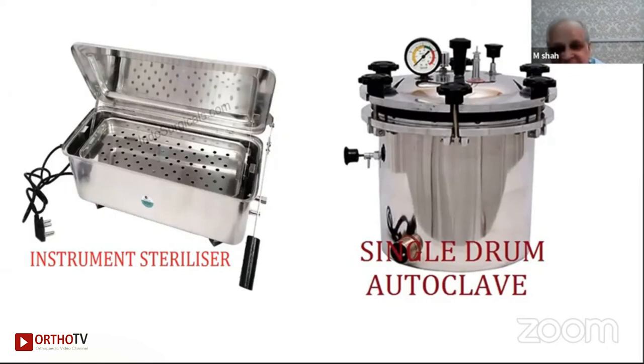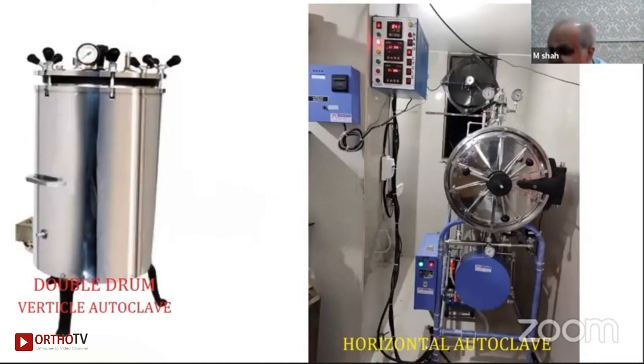World War ended. The researches went on. In 1935 to 45, again World War II came. But before that, there were some researches, and ultimately people came with a vertical autoclave, which Saab has spoken, Siddharth has spoken. No need to go into detail, but vertical came in somewhere near 1930. That also could not work because vacuum could not be created. Why? Because of the steam that is generated, and underneath there is a boiling tank. Whenever these two are there, the pressure can go only to a limit, not to kill the resistant or virulent bacteria. So slowly it got displaced in the Western world, and then came the horizontal autoclave.